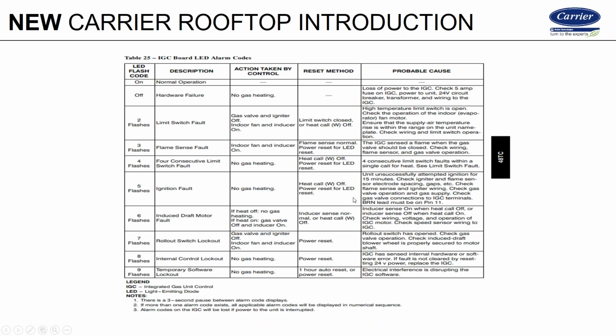The fault codes that it has, we'll go through that. So the LED, you've got one red LED light on this IGC board. That should be on solid if everything is good. If it's off, either you don't have power to the unit, or there's some kind of hardware failure, or the LED itself has failed. But as far as actual fault codes, you've got fault codes 1 through 9. 1's really what's called an indoor fan modification, which doesn't mean anything, and it doesn't mean that you've modified the fan.